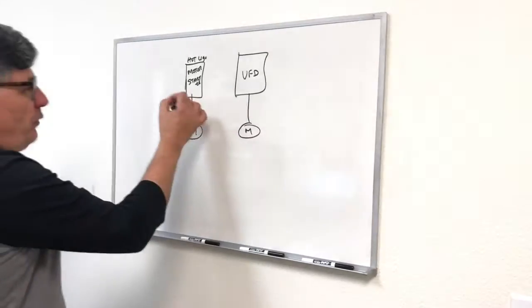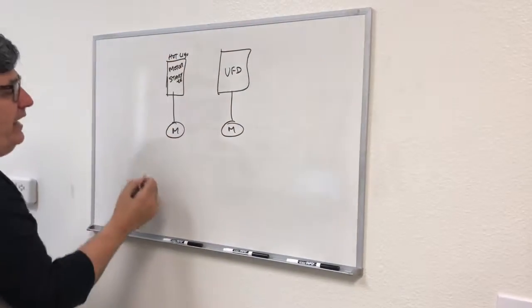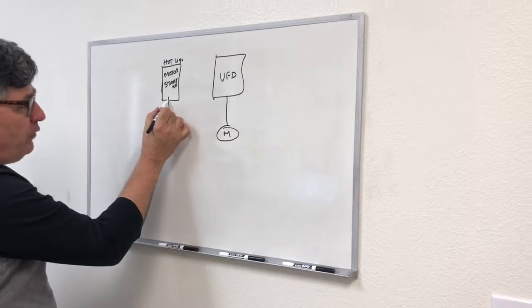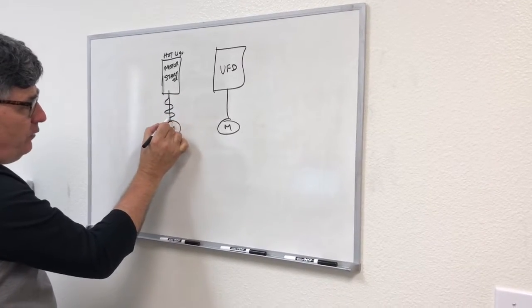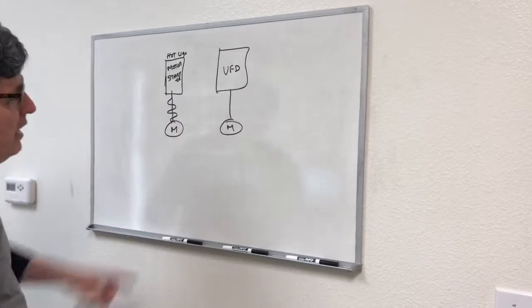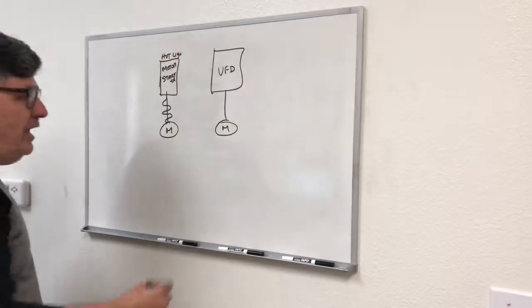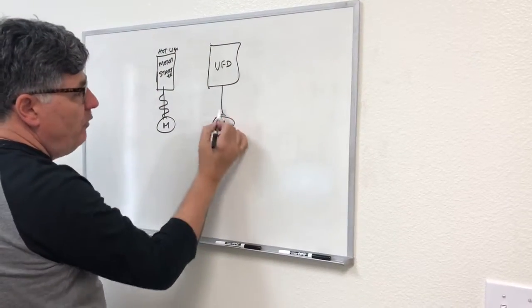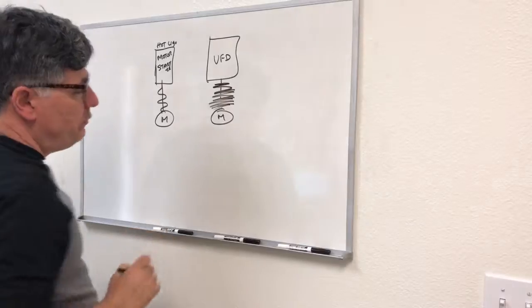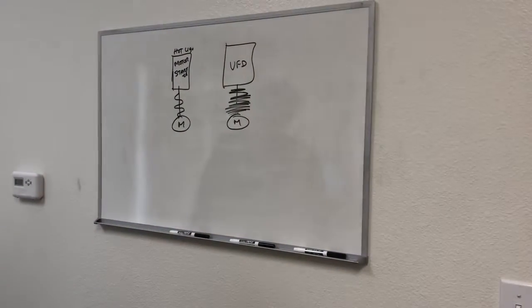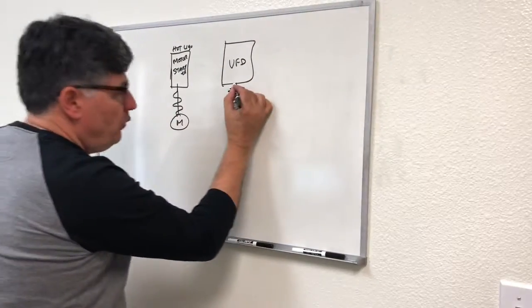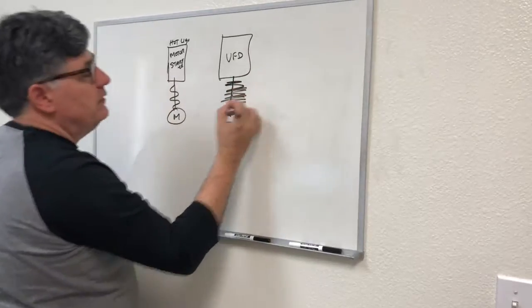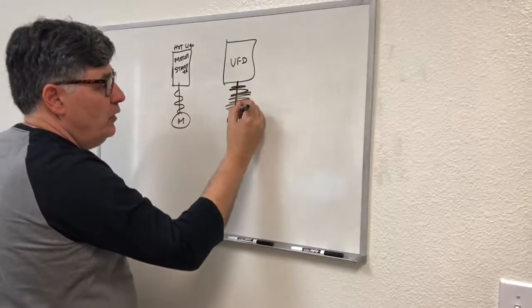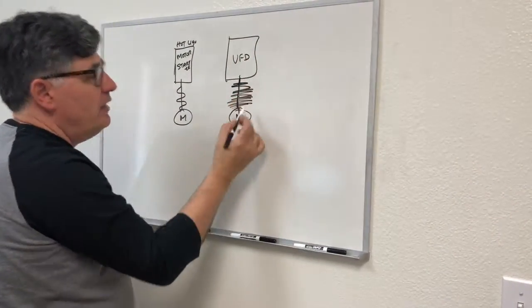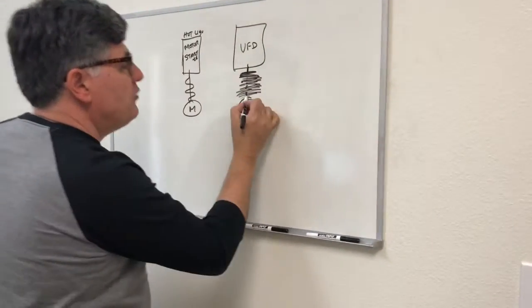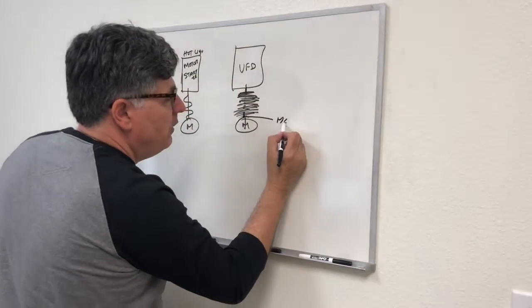Now, when you're using a regular motor starter, like on the hot liquor tank, when you turn it on, the power flows to the motor with a really nice sine wave like that, really nice and smoothly. But when the VFD is turned on, the power goes to the motor like this. It's a really crazy wave like that. And because of that, of course, these are wires, a piece of metal, if you will, from the VFD to the motor, and this crazy waveform turns this wire into a magnet.